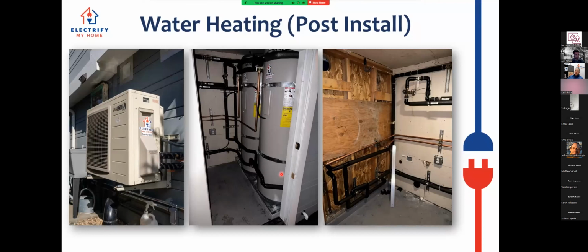So if we would have put two heat pump water heaters in here at 30 amps each, unless we went with plugins, and those weren't available at the time, we would have been utilizing 60 amps of capacity derated to whatever it would have been. But with this unit, it's one 15 amp unit that's fully modulating, extremely quiet, remote right outside the closet, heating up 83-gallon tanks, 166 gallons of water, and keeping everything nice.